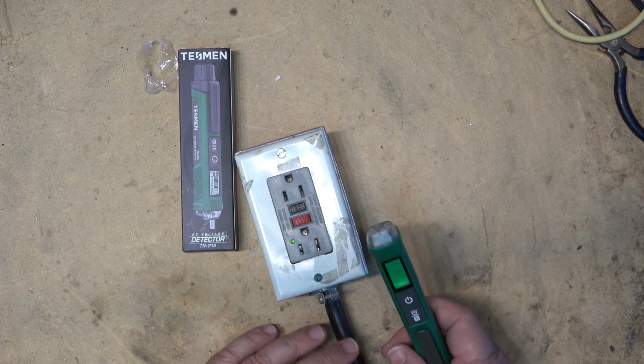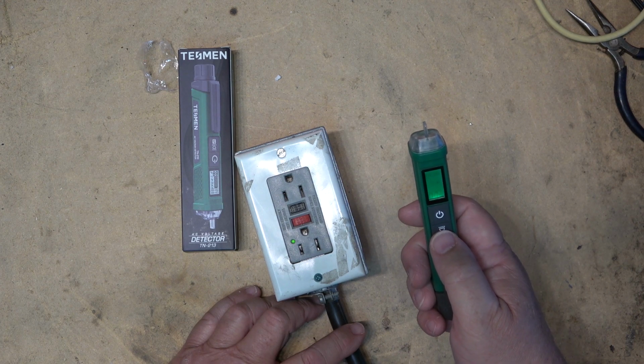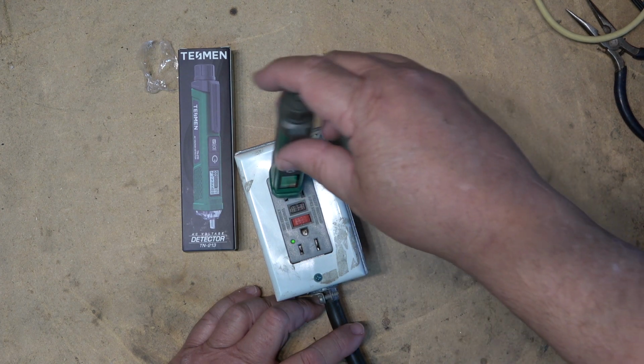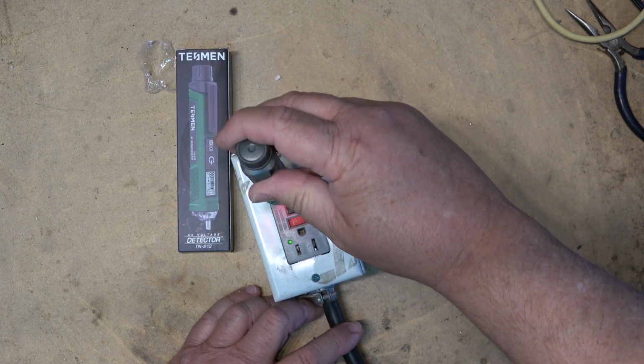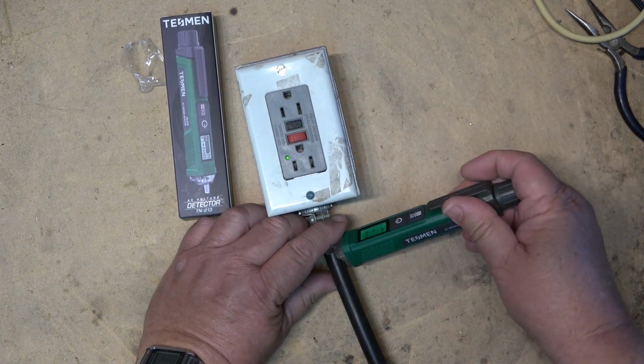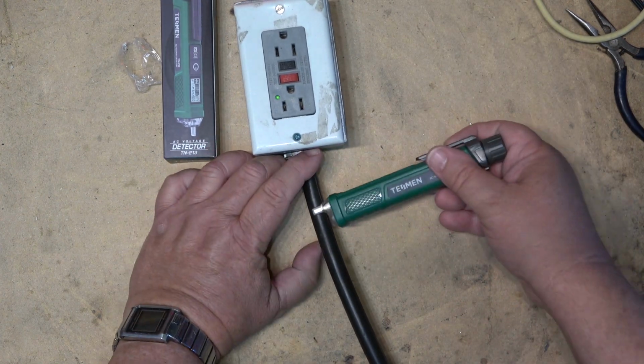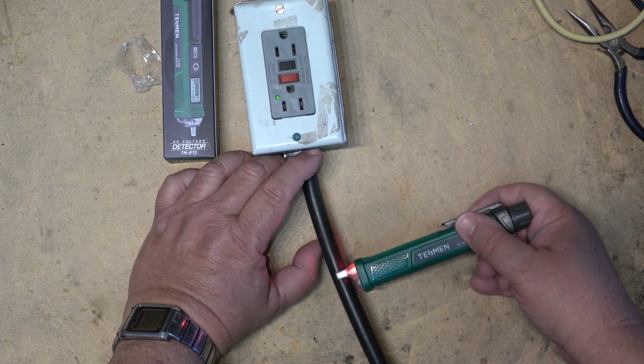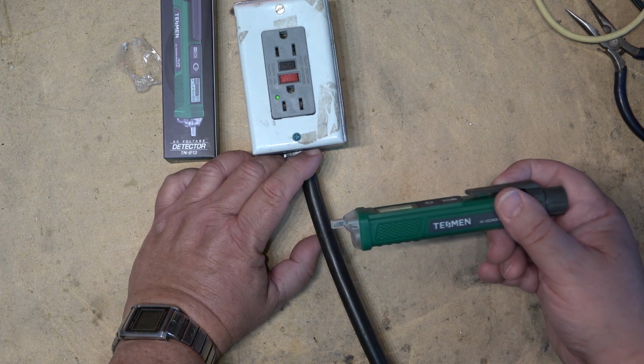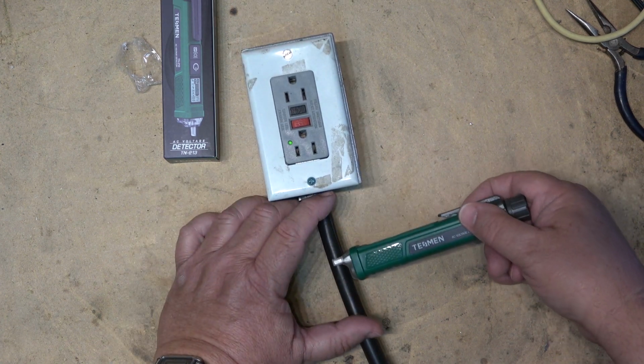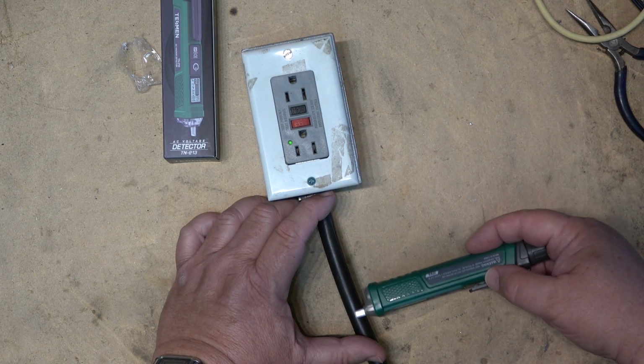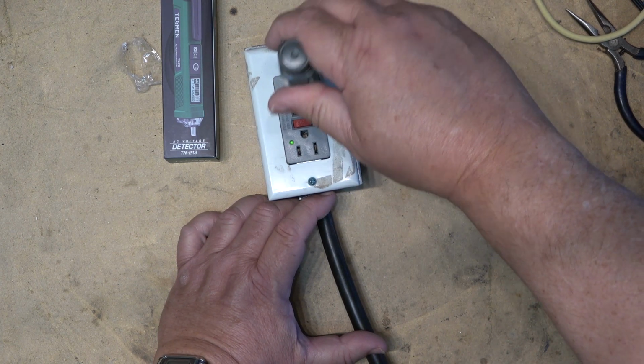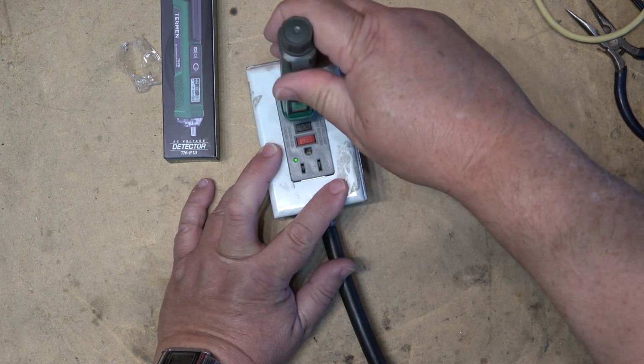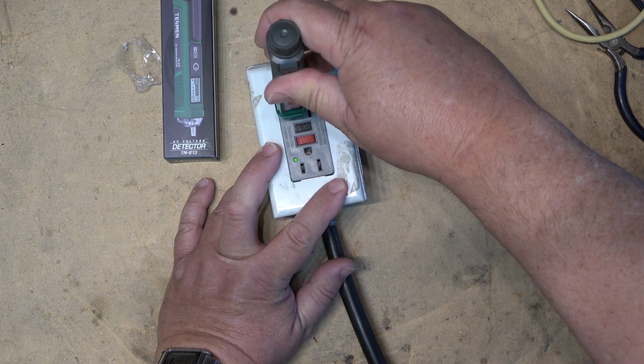Now I'm on the high sensitive mode. If I switch it to 70 to 1 kilovolt, I have to actually make contact to tell me that the wire is live. It probably won't detect anything here because of the insulation. Oh, it was able to detect a little bit there. But you won't get anything if you put it into the blade here until you hit the hot side. Neutral side shows nothing, the hot side should light up, which it does.